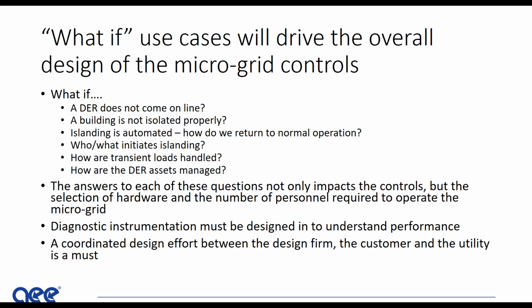Islanding is automated - how do we return to normal operations? If you're connected to a utility and you cut out of a substation, you've detected a power outage, severed the link to the utility, you're going to go into island mode. Well, the utility comes back an hour later, two hours later, two weeks later - how do you go back? Do you do it automatically? A lot of utilities don't particularly care for that. What's the process, what do the controls do? Don't know. Who initiates the island - is it automatic? If I detect a power loss for some number of minutes, do I island? If I detect it instantly, do I island? Do I island proactively based on a storm front coming?